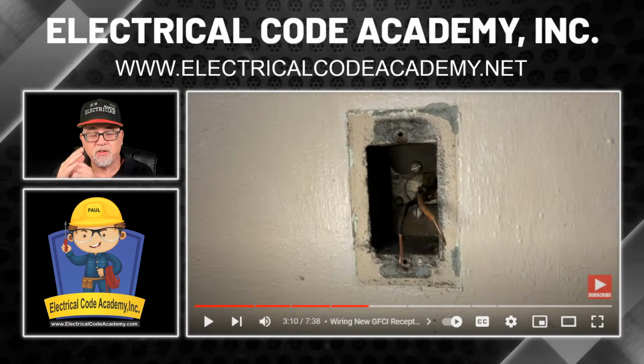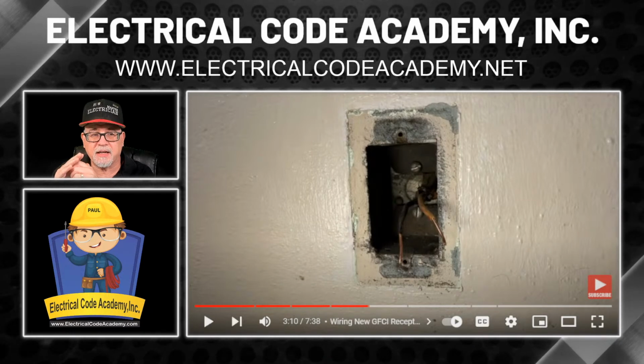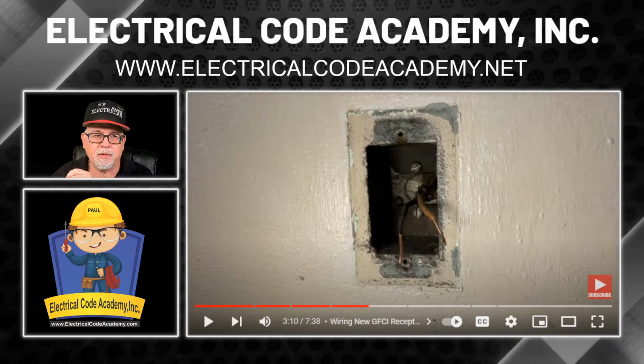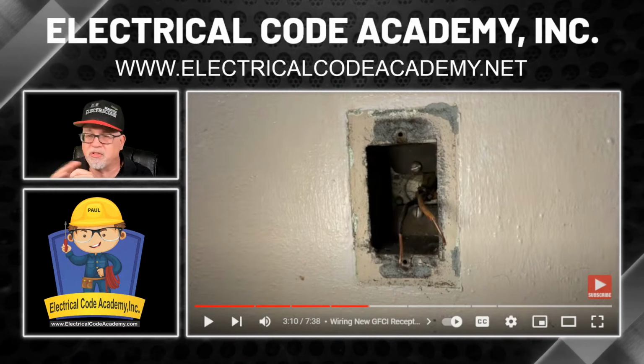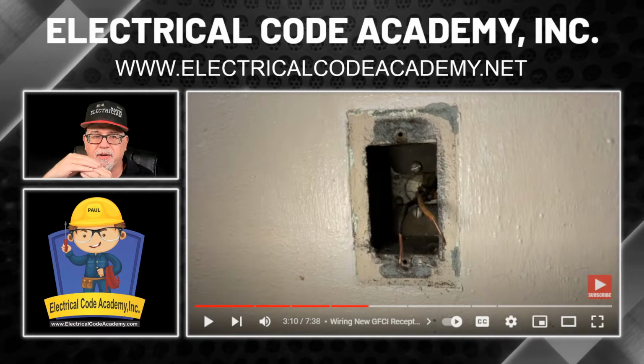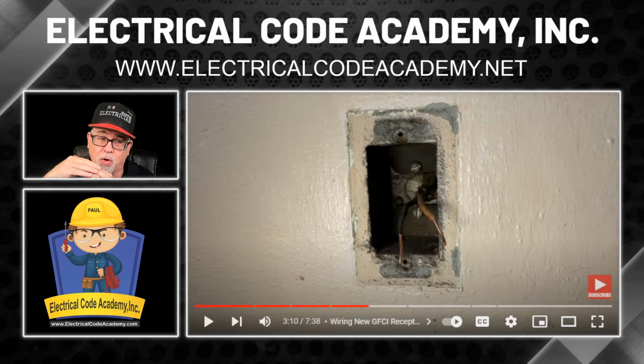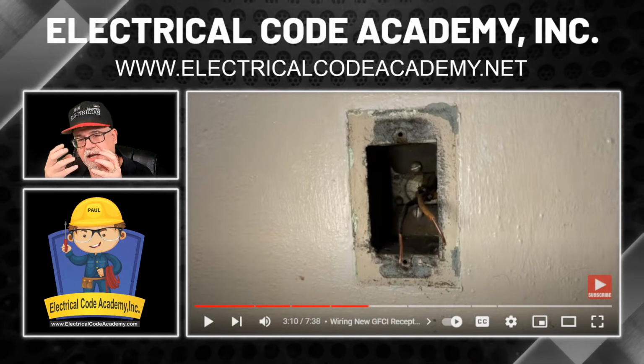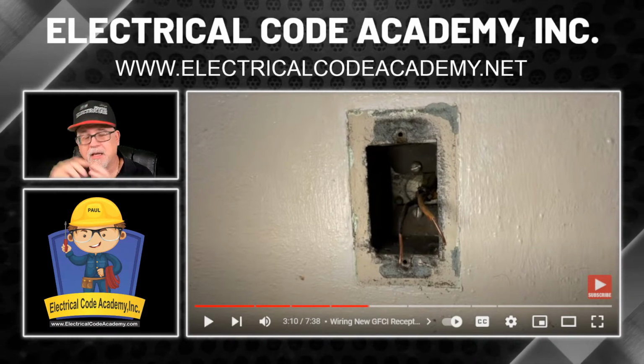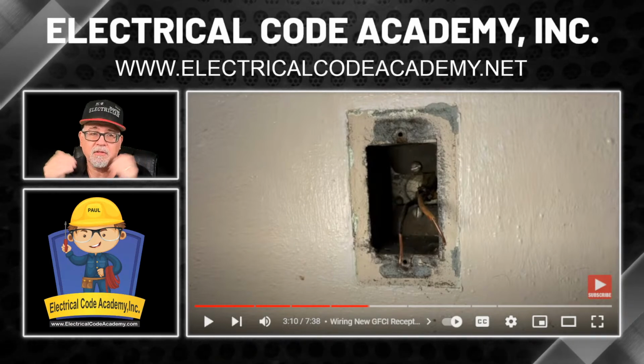So when it gets to the end, you just take that aluminum grounding/bonding conductor and cut it off. You don't do anything with it. You don't take it in the box, you don't terminate it, you just cut it off. And then you put the proper MC-A fitting on top of it, and then it makes intimate contact with the armor, with the fitting, and with the box, and you're done, right?